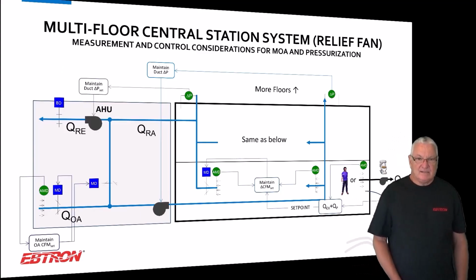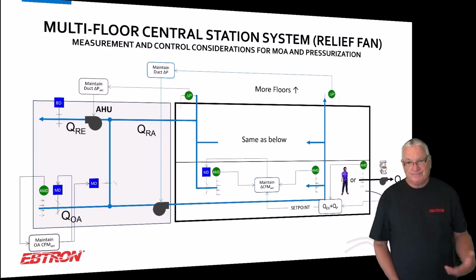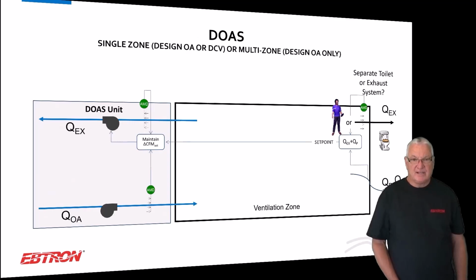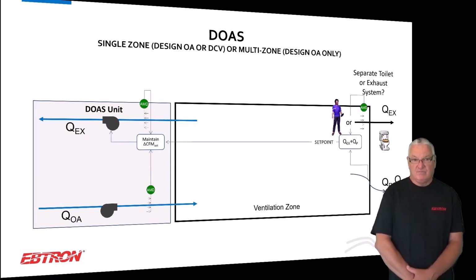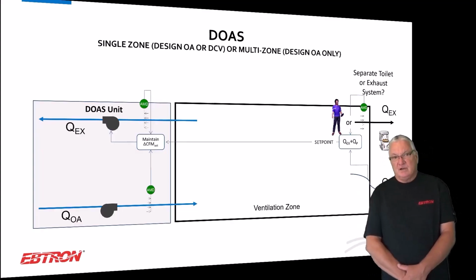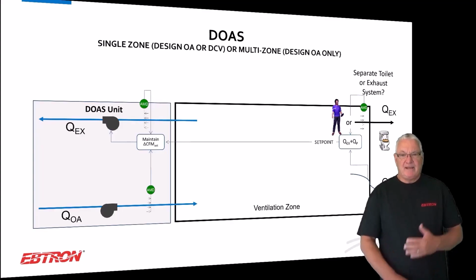Again, we got supply. It doesn't matter to me if it was a supply return system or a supply relief system. We're going to do it the same way. DOAS, putting DOAS in because I think it's very important to look at DOAS, particularly with energy recovery. I've seen too many systems with energy recovery that bring in plenty of outdoor air but ignore the differential, get into a humid climate, and the next thing you know, the walls are soaking wet. Okay, you got big mold problems. Right, you got to pay attention to both.